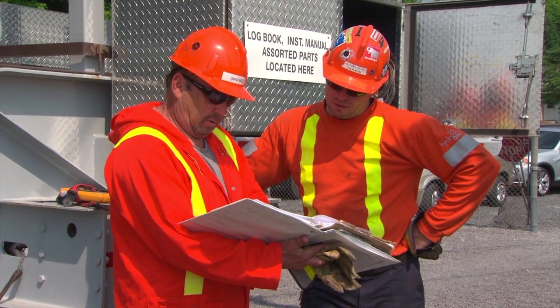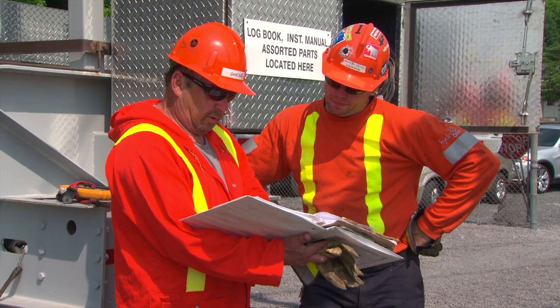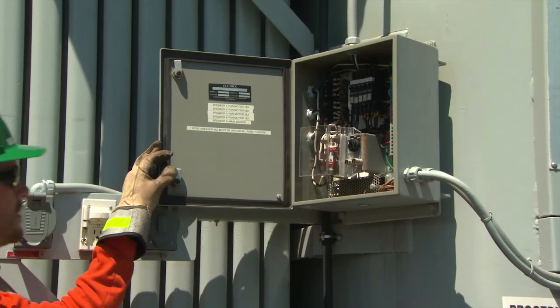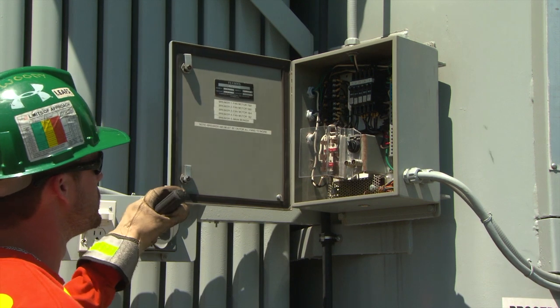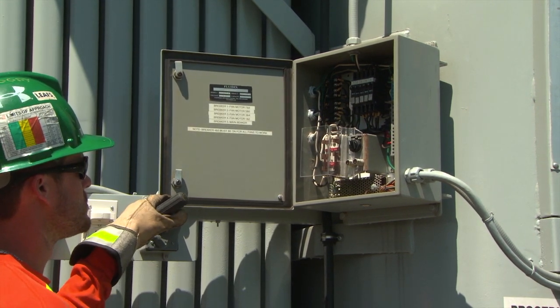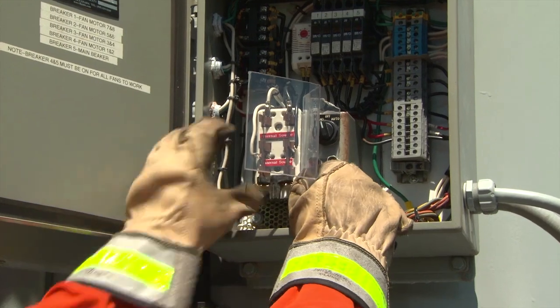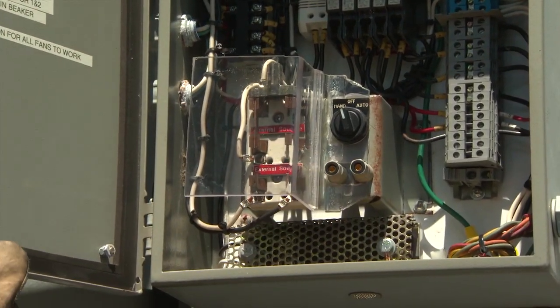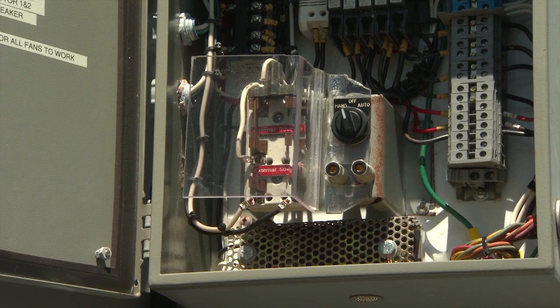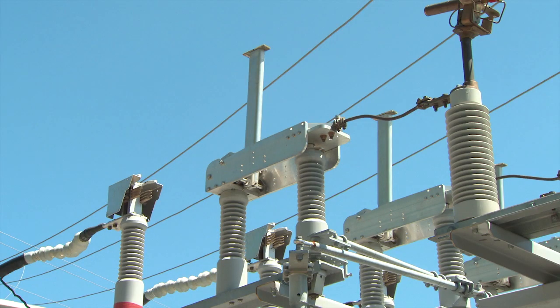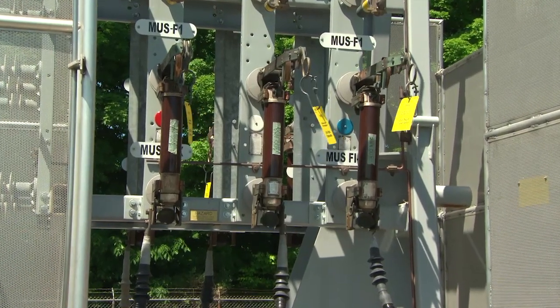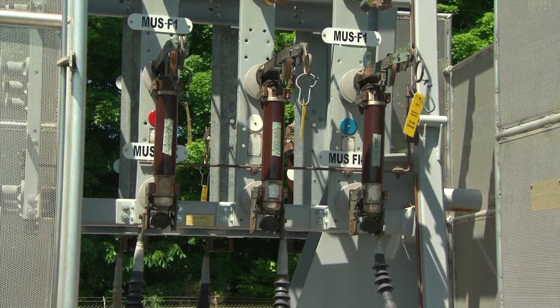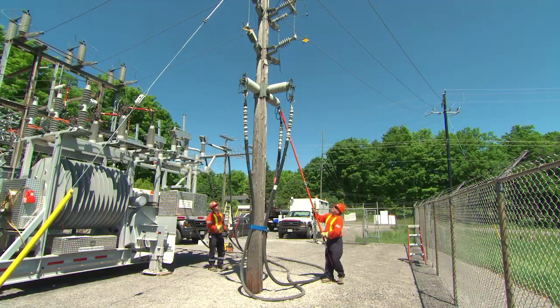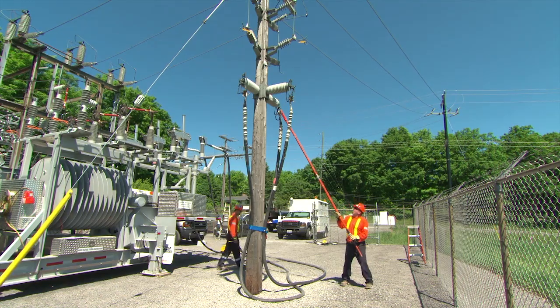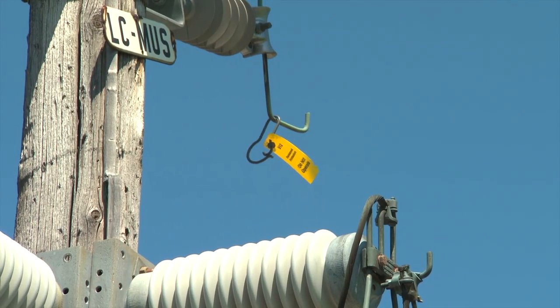Prepare and check an OTO for switching the MUS into service and the DS out of service. Check that the external supply is disconnected and the internal-external switch is set to internal. Check that the high-voltage disconnect switch is open and locked. Check that the low-voltage feeder disconnect switches are open and locked. Remove work protection tags on the LC-MUS loops and then close the loops.